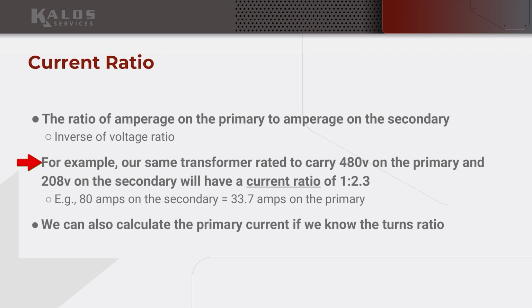Now, of course, this is a perfect scenario where there are no losses inside the transformer, which is not the case. So it won't be an exact 33.7, but you're going to be in that range of 33.7 measured on the primary. This is sort of an aside, but if you wanted to measure those losses, you would take a reading on the primary current, and then take a reading on the secondary current, and then figure out the difference, whatever is lost in the transformer. It probably is more sophisticated than that, but that's generally how you could figure out your losses inside of a transformer. Although we typically, as electricians in the field, aren't overly concerned with that.